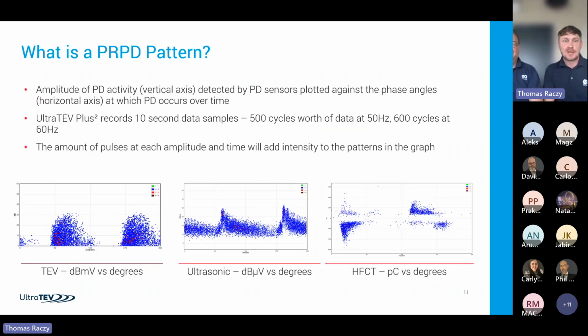We're back. Okay, so a PRPD pattern is an actual display of the amplitude of PD activity on the vertical axis, as detected by various PD sensors, as per the example shown in this slide. So that could be the TEV, so internal discharge, ultrasonic, surface discharge, HFCT, etc. The amplitudes of those signals are plotted against the phase angles, the horizontal axis, at which the PD actually occurs over time.